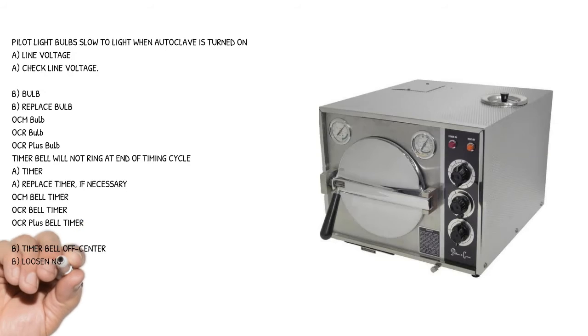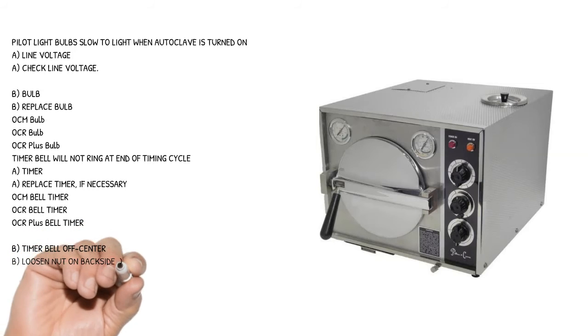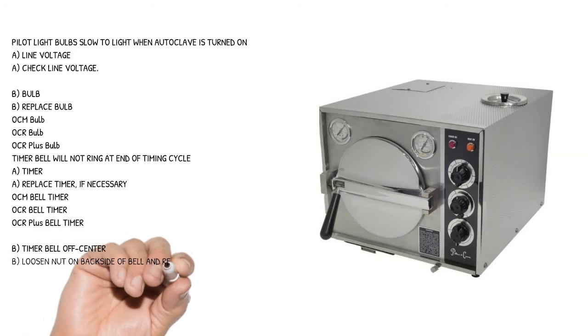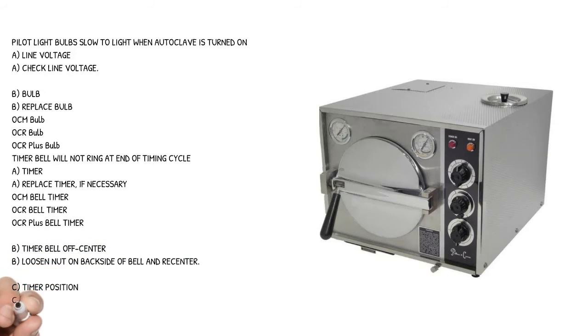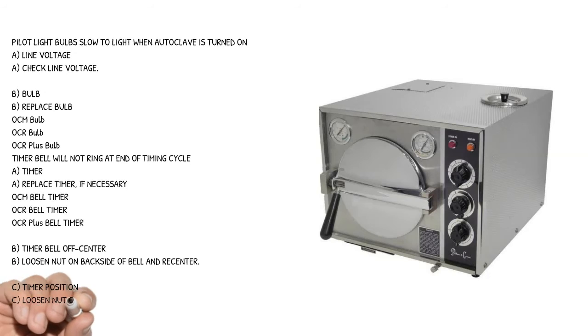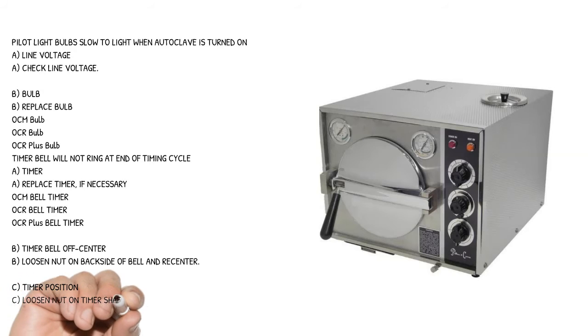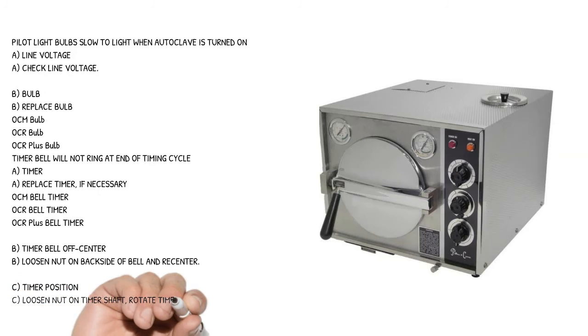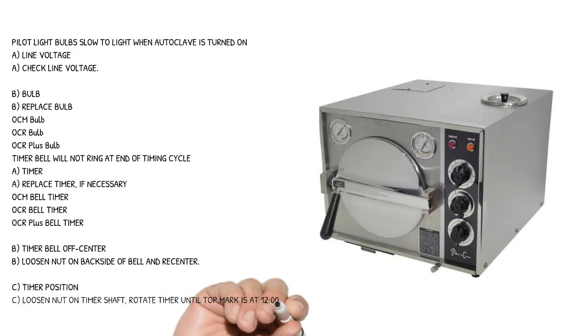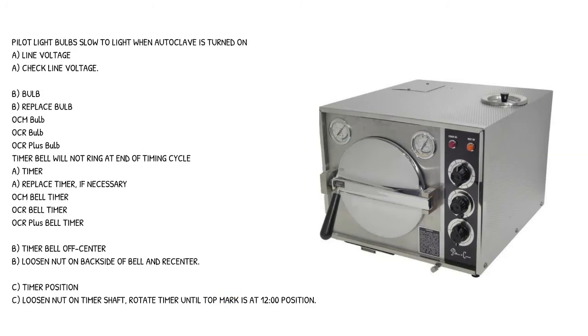Cause B: timer bell off center - loosen nut on back side of bell and re-center. Cause C: timer position - loosen nut on timer shaft, rotate timer until top mark is at 12 o'clock position.